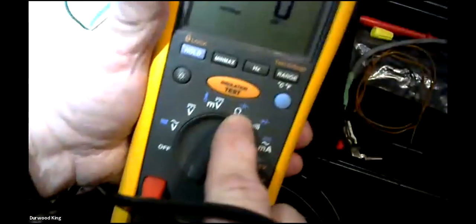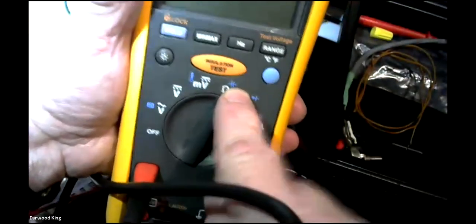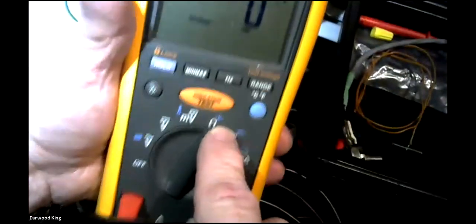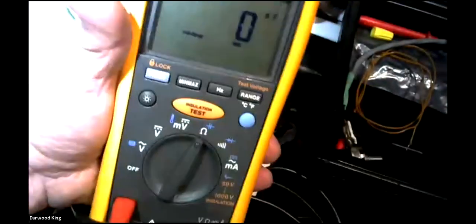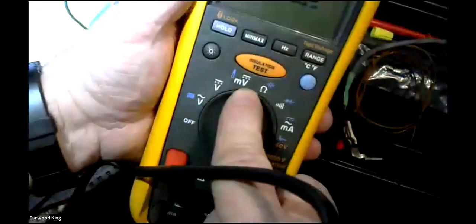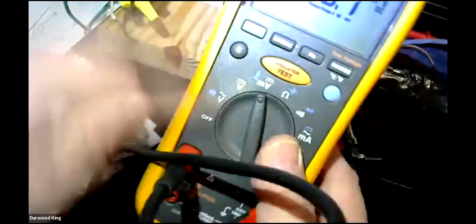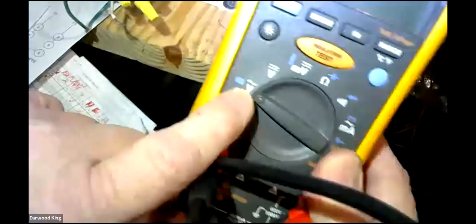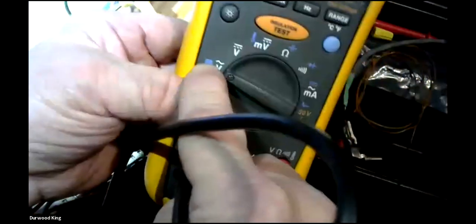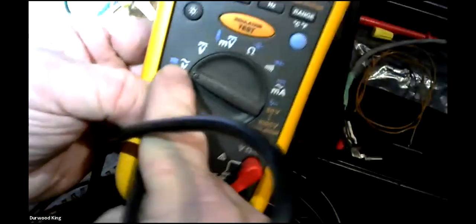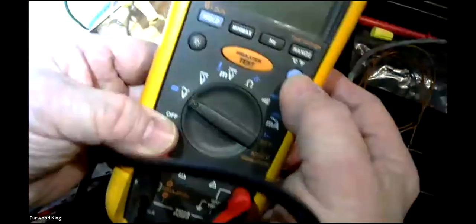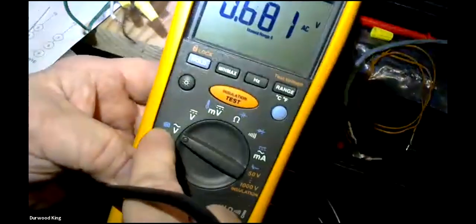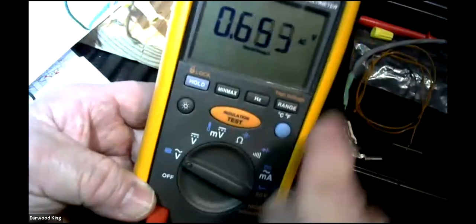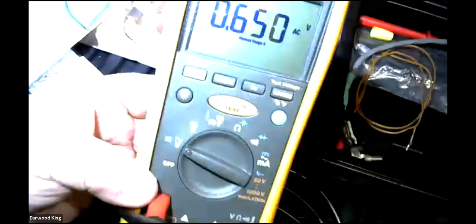It checks capacitors. Capacitors are on single phase motors to give them a booster. You can take a capacitor out of a single phase motor and check it here on the blue function, and it'll tell you the microfarad reading. It does millivolts. It does temperature readings in the blue. It does DC voltage, AC voltage, and then in the blue it does low pass voltage for VFD.